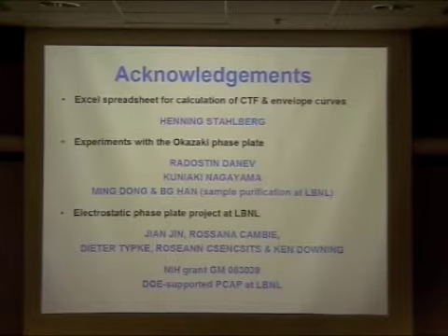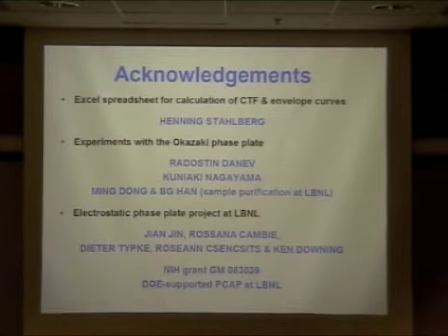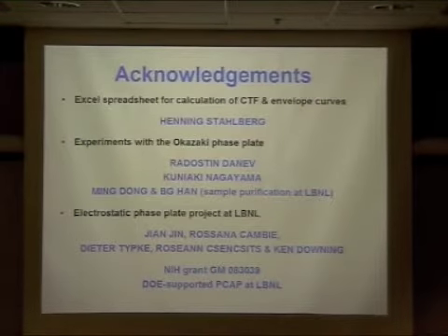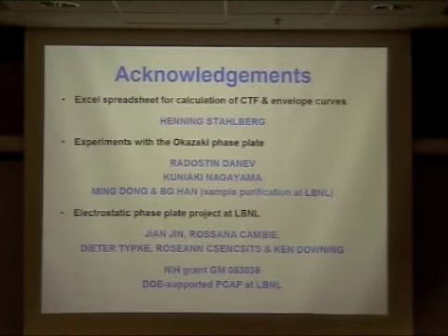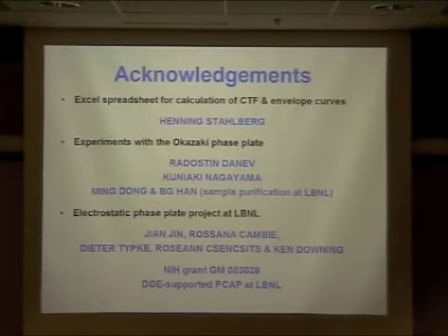So, in summary, is it correct to say that if you're looking at Cs correction of phase plates, if you insert the phase plate, you're recovering the phase shift within the normal framework of the normal CTF that we normally see, but if you include the Cs corrector, it allows you to go on to a higher resolution? Yes. Except for the previous thing you said: if you have the phase plate and you're in focus, there is no CTF correction at all. Right. There are no oscillations.